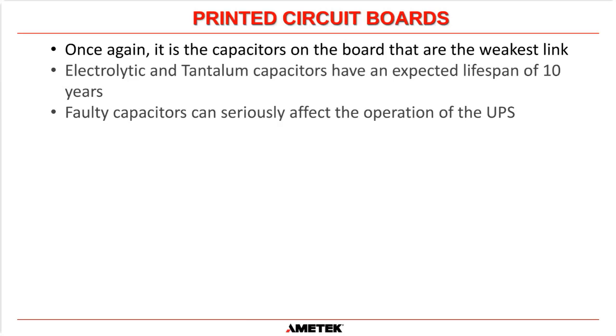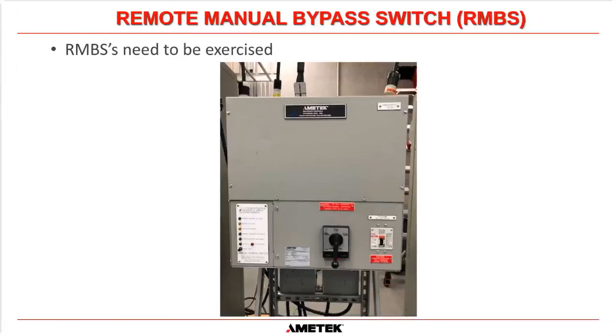And obviously, I've gone over that electrolytic and tantalum capacitors have 10-year lives, but faulty capacitors can seriously affect the operation of the UPS. They can cause the system in some circumstances to transfer to bypass, and once you're in bypass, you do not have battery backup. So if you had a power failure, then you would drop the load, which would cause an unplanned outage. So we want to make sure that that never happens. So that's why we have the time frame of 10 years to replace capacitors and PCBs.